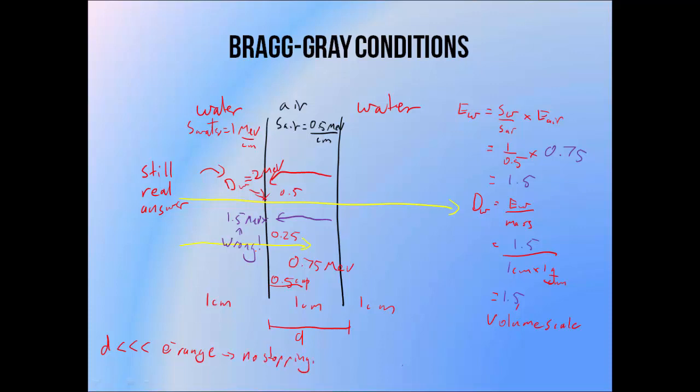This is also why we don't want any changes in electron energy deposition within the chamber — since if it's higher in one part of the chamber than in another, we can't accurately apply volume scaling. So the electron range must be much larger than the dimensions of the chamber. Electrons shouldn't stop inside the ion chamber, and we don't want any electron energy changes inside the chamber either, otherwise the Bragg-Gray relation combined with volume scaling will give us an incorrect result.